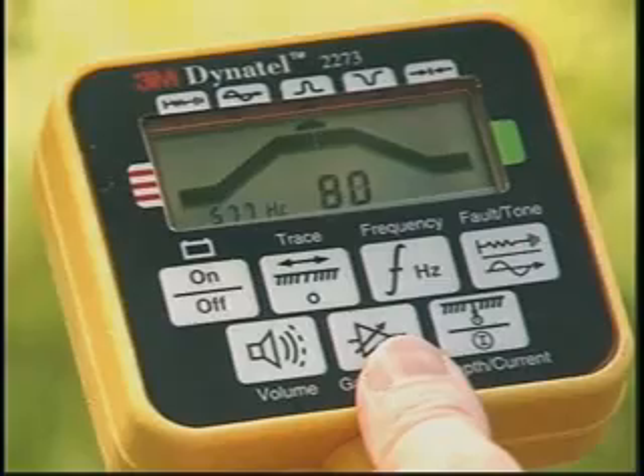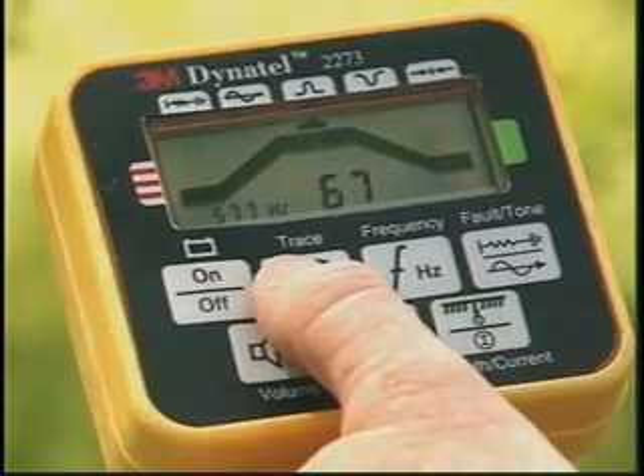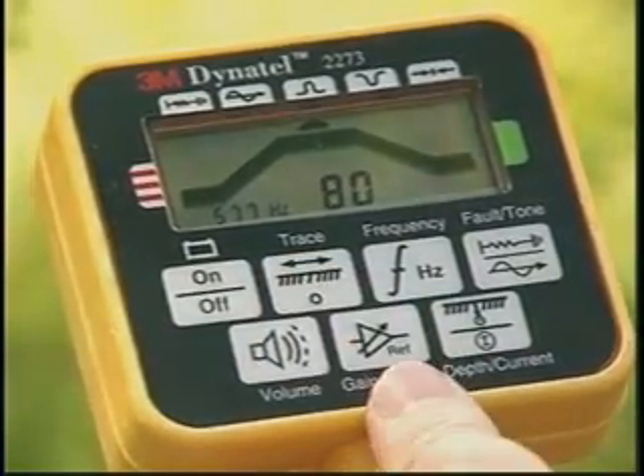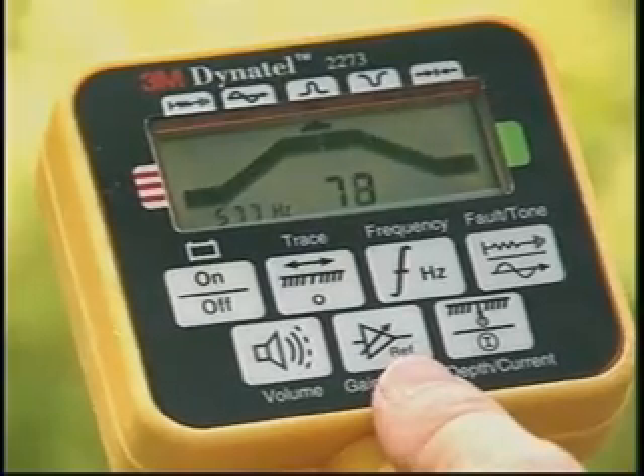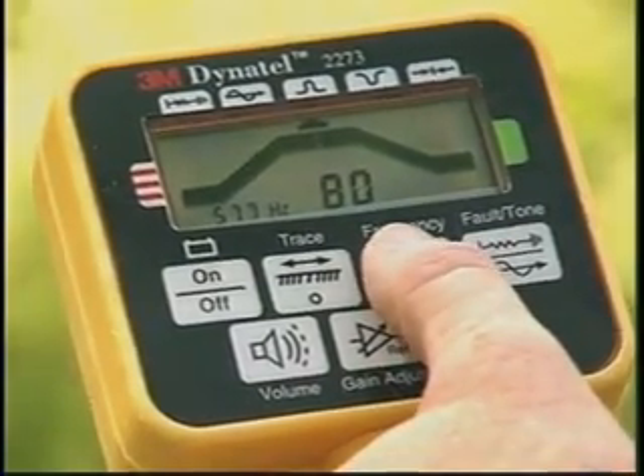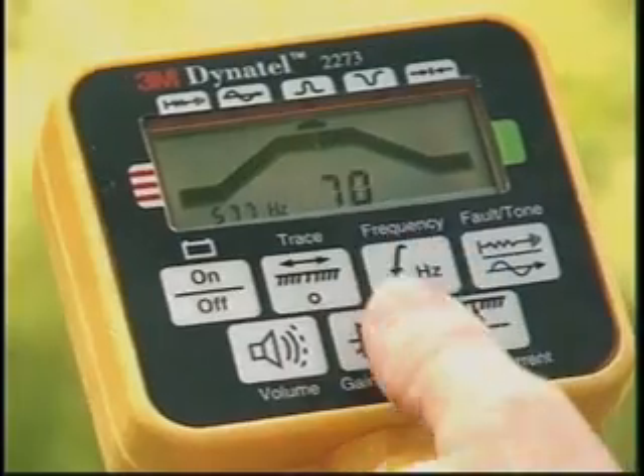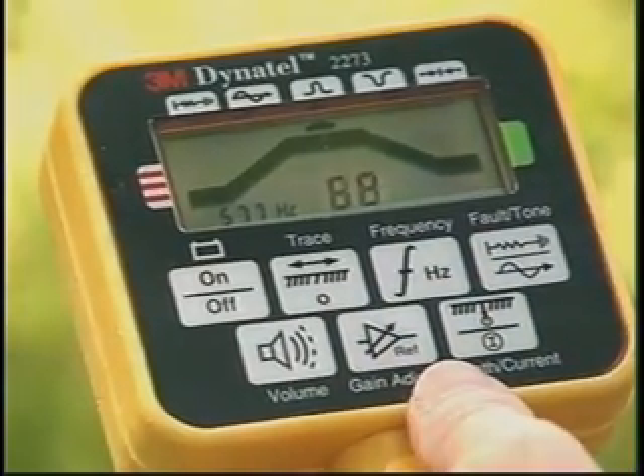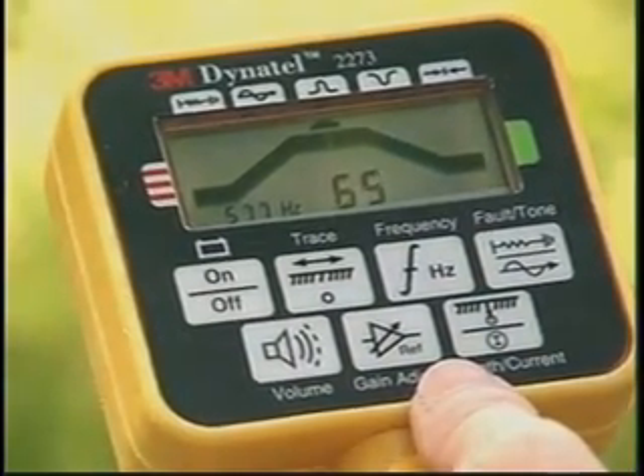First, select one of the 4 trace modes. Here, I'll use peak. Next, set the receiver's frequency to match the transmitter's output frequency. If you're tracing a power cable without using the transmitter, select the power frequency.